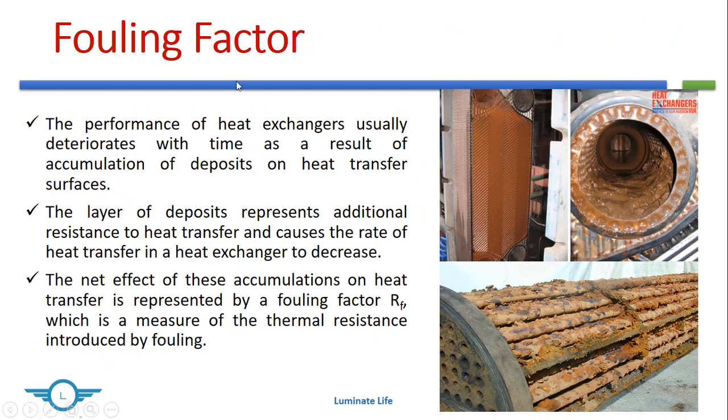Now one of the problems with the heat exchanger is that over time some sedimentation will develop on the heat exchanger walls, or outside the pipes of the heat exchanger. So what will these sedimentations cause? They will add an additional layer of resistance to the transfer of heat flow. Earlier we were only considering the convection resistance inside the pipe, the conduction resistance of the pipe, and again the convection resistance outside the pipe. But now there is a layer of sediment on the inside of the pipe, and there might be a layer of sediment on the outside of the pipe.